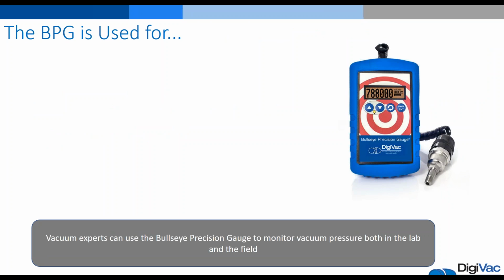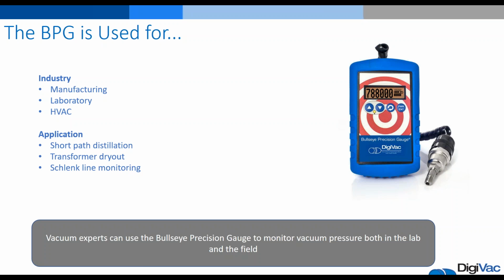So what is the Bullseye Precision Gauge used for? It's used in a few different industries, and those industries are manufacturing, laboratory, and HVAC. There are other industries in which the gauge can be used, but those are the most popular that we see amongst our customers. And the applications in which the gauge is used are for short path distillation, transformer dryout, and Schlenk line monitoring. So vacuum experts can use the precision gauge to monitor their vacuum pressures both in the lab and in the field, meaning if they need to go somewhere and test a vacuum system, they can do so with the Bullseye, or they can test it within their own lab on their own property. And it's also used to manufacture on an HVAC line.